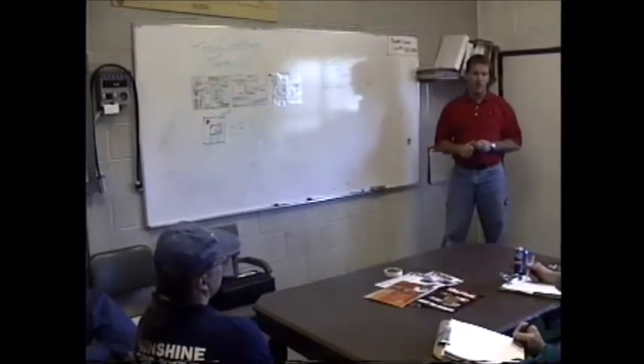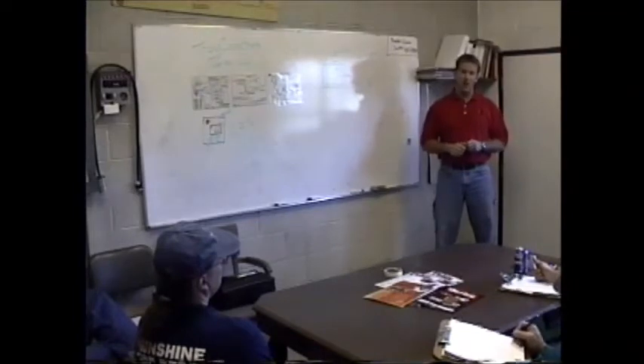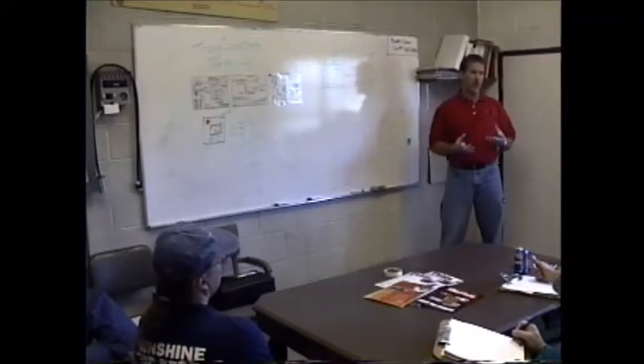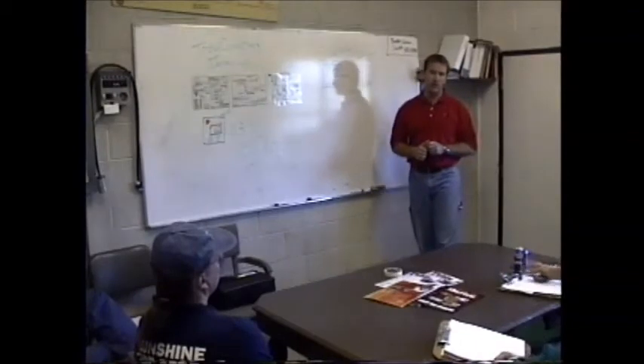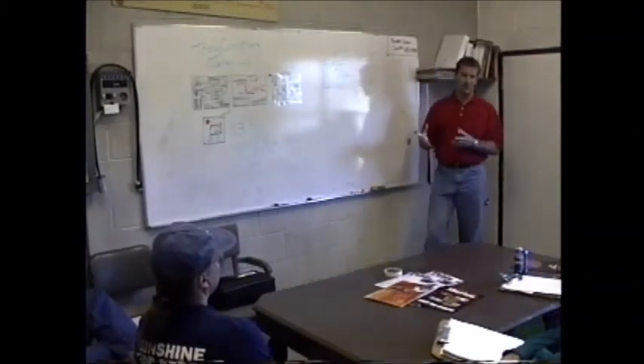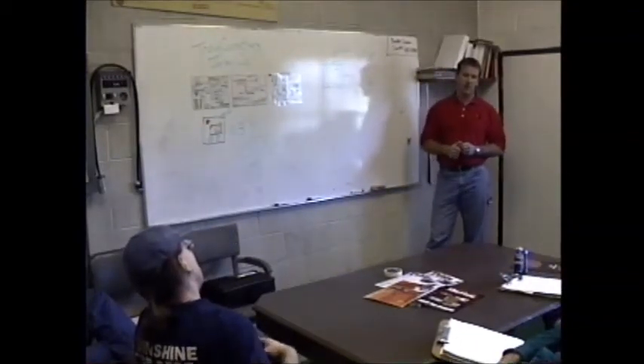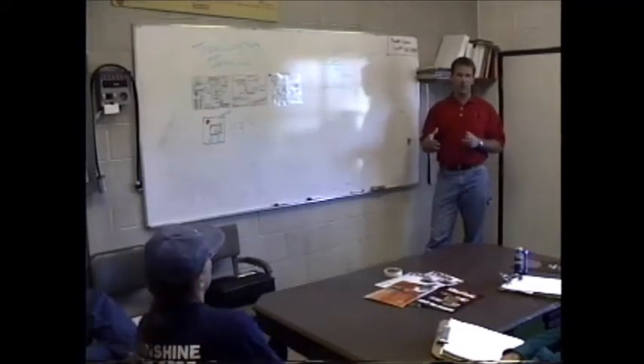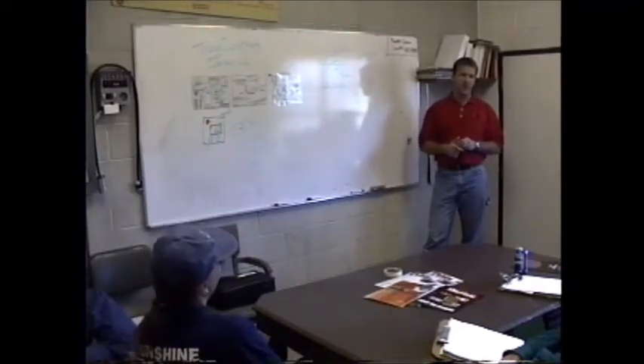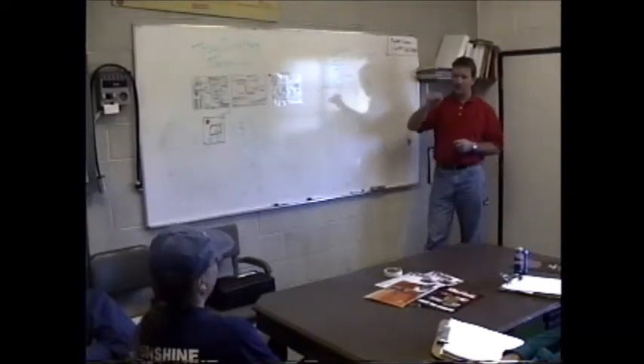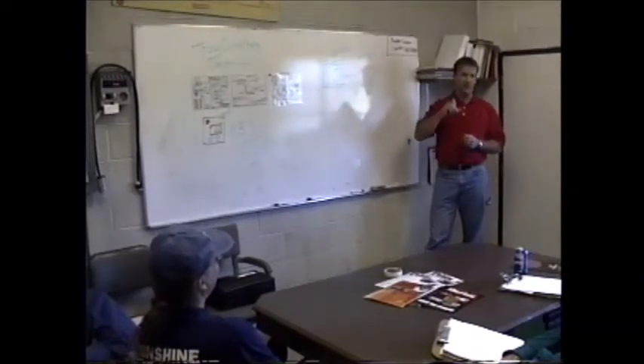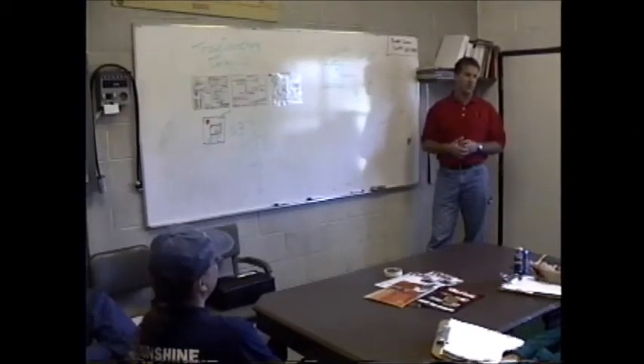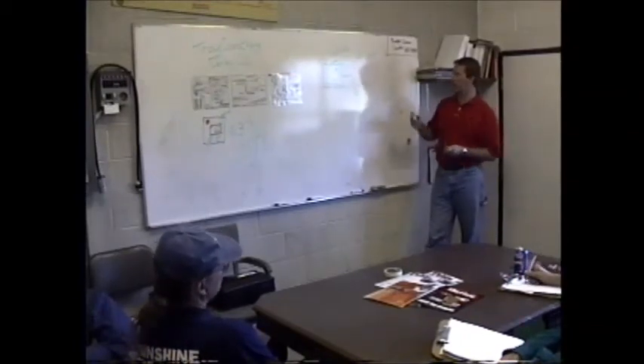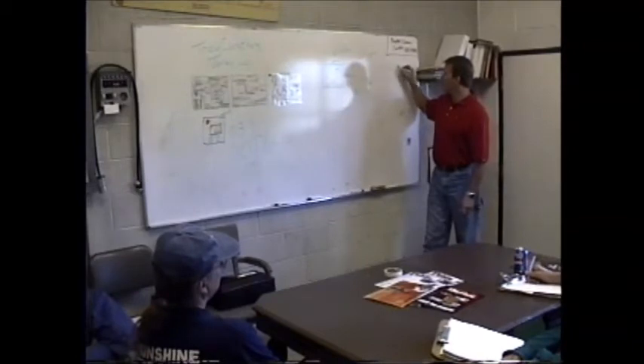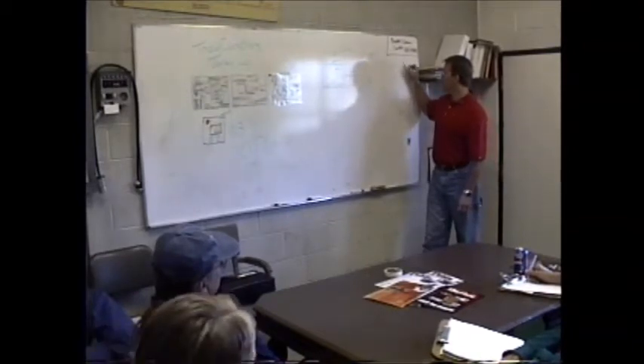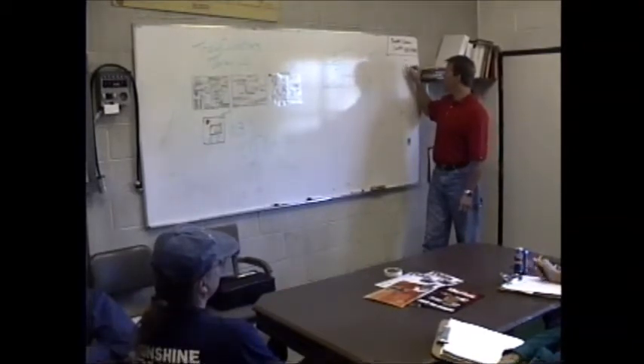And that's a 1 3/4 inch, what about 1.5? It's not all that much different. With compressed air foam, the 1.5 inch and 1 3/4 numbers really don't vary that much. And that's where I kind of threw out that 125 number. The 1.5 was always about 120, but if you go to 1 3/4 hose, you get about an extra 5 parts of something in there. And it's negligible when you're looking at graduated lines that are 1/8 of an inch apart. You're not going to see that much of a difference. You can still pretty much figure you get 120 parts for either 1.5 or 1 3/4.